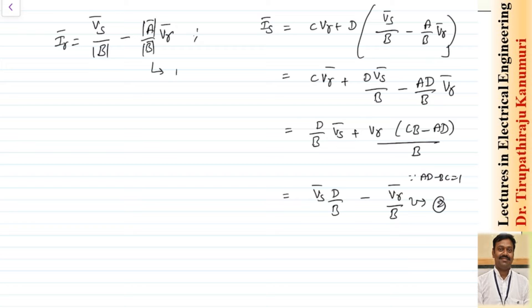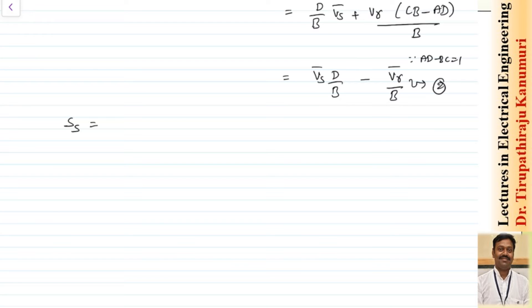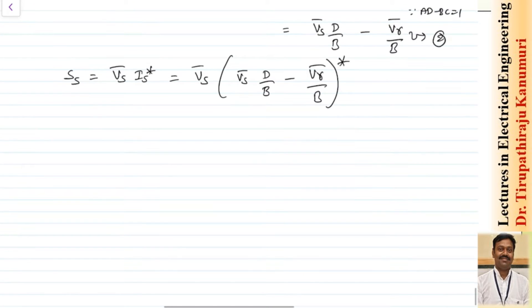Now the sending end apparent power Ss = Vs × Is*. Substituting Is from equation 2: Ss = Vs × conjugate of [(D/B)·Vs − Vr/B]. The conjugate means we take the angle as a negative angle. The reason for taking the conjugate when multiplying voltage and current is to obtain the angle difference between voltage and current — this is why S = V·I*. A reference to the basic electrical engineering lectures explains this in detail.